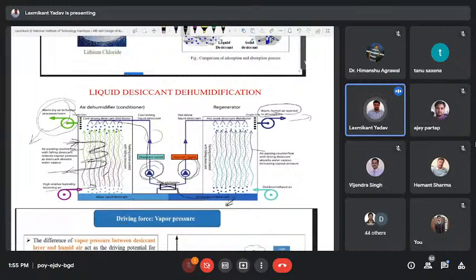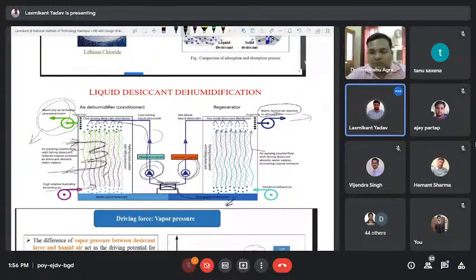So this is the basic working of a liquid desiccant dehumidification system. As you can see, this system is slightly complex, like the vapor absorption system we have already studied in RAC. Vapor absorption systems use low grade energy, but they are complex. It occupies large space because it requires the absorption chamber, regeneration chamber, pump and some ducting work. Also this desiccant is corrosive in nature, so corrosion of the duct may take place. This system can be driven by solar energy or a heater, but it is complex in nature.